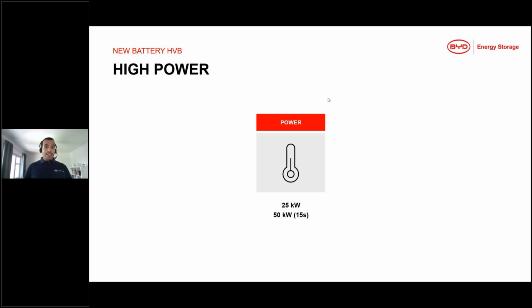Now, reliability and capacity is not everything. So you can have up to 30 kilowatt hours in one tower, which is super small, but 30 kilowatt hours, that's just energy. If you want a system that is able to cover every load in every critical situation, like for example in blackout situations, you don't only need high capacity, you also need high power. And the HVB has high power. So if you have a system of 30 kilowatt hours, so 10 modules in a tower of 1.3 meters in height, it's possible to have a power of 25 kilowatt rated nominal, with the possibility to double that power for a time duration of 15 seconds.